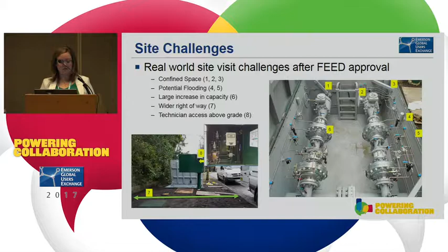Everything's right there for those technicians. Since they probably won't have to work on this very frequently, we put the operational schematic on magnets and a laminated copy right on the side of the door. So if they do have to come out to this 10 years from now at 2 o'clock in the morning for something, all the information they'll need for troubleshooting is right there. It's all color-coded and mapped to the station in the real world, so everything is tagged with tubing colors according to that color schematic on top.